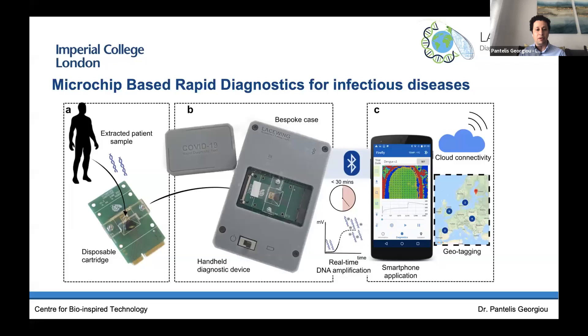We take this cartridge and here's our handheld device, which we call Lacewing. The cartridge plugs into our handheld device. This is actually the first handheld molecular diagnostic able to interrogate a sample and amplify DNA and RNA in real time. What's unique is it can detect the target in under 30 minutes. In real time, at the moment of detection, we geotag the result, upload it to a mobile phone, and that goes up to our cloud server. In real time, we map where the infection has taken place. We were doing this before COVID — and I'll show you results from our trials in Ghana for malaria. This lends itself very nicely to testing in the community — in schools, airports, and different settings — for rapid diagnostic and screening of infectious diseases.